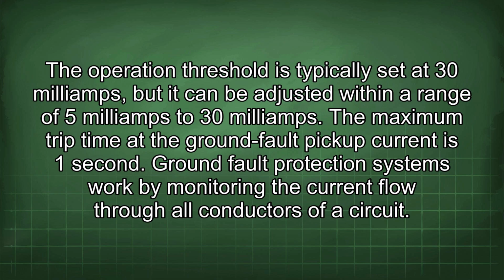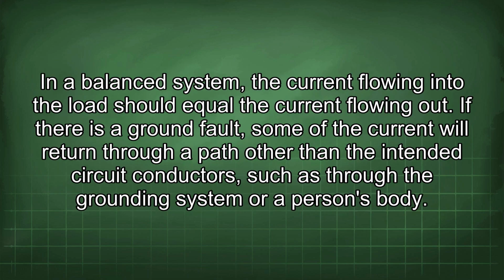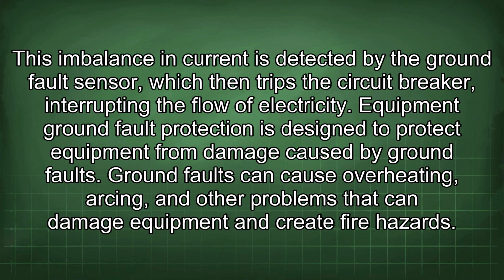Ground fault protection systems work by monitoring the current flow through all conductors of a circuit. In a balanced system, the current flowing into the load should equal the current flowing out. If there is a ground fault, some of the current will return through a path other than the intended circuit conductors, such as through the grounding system or a person's body. This imbalance in current is detected by the ground fault sensor, which then trips the circuit breaker, interrupting the flow of electricity.